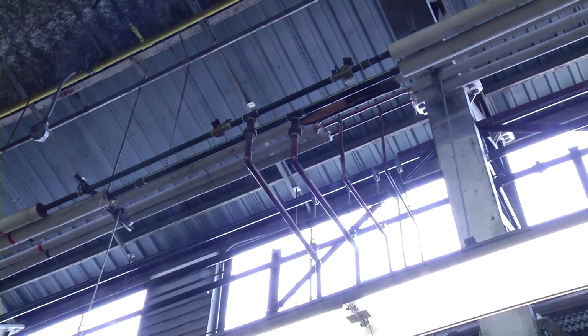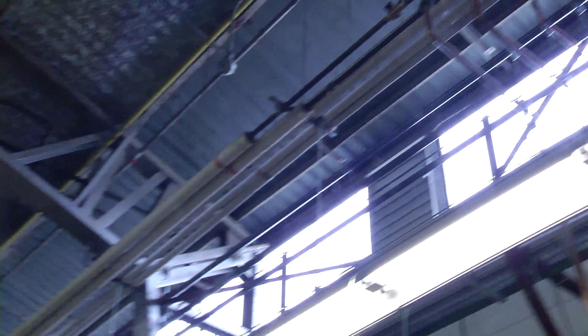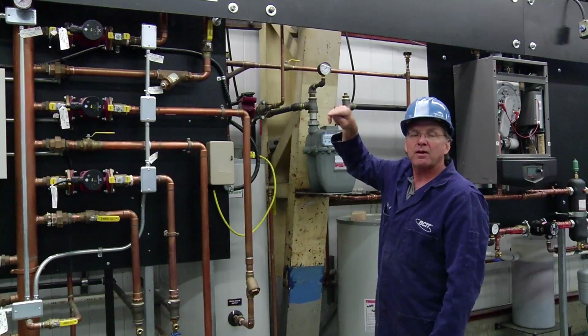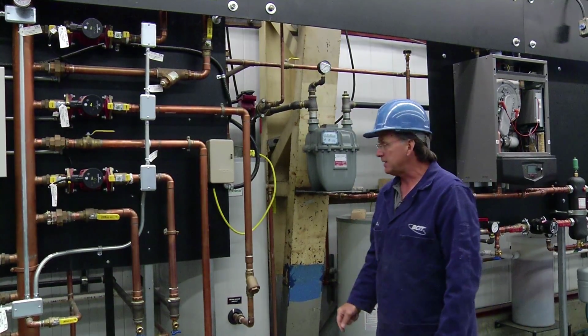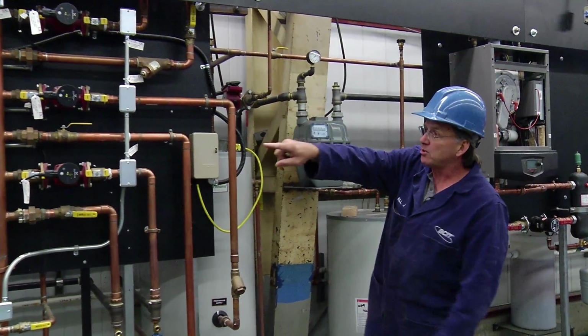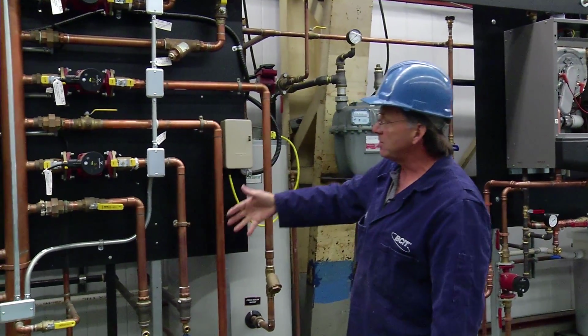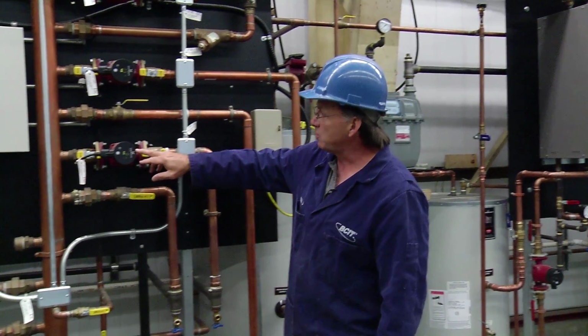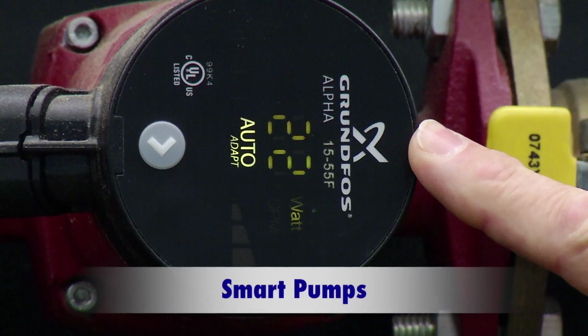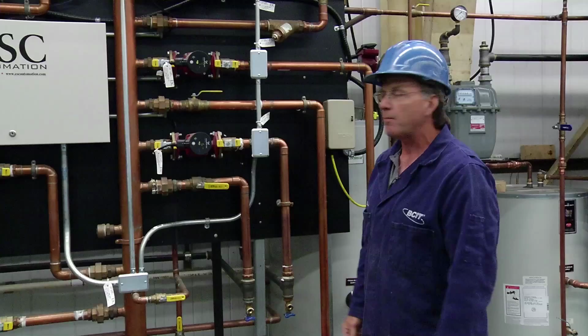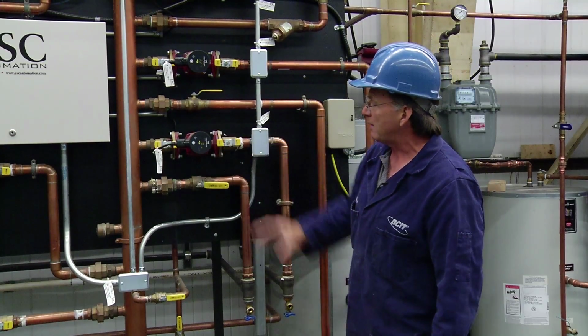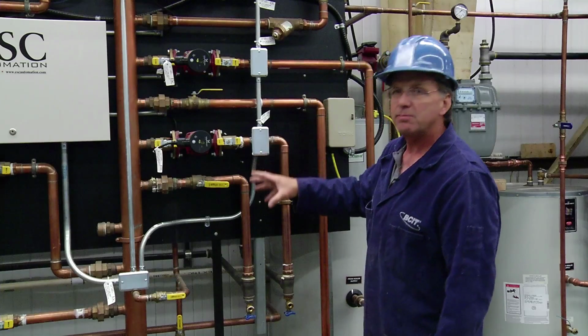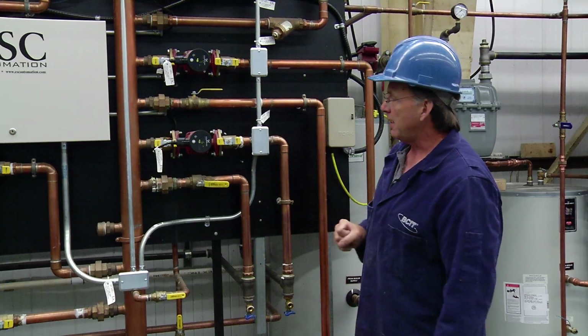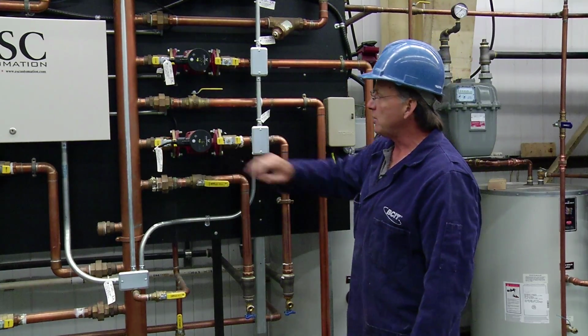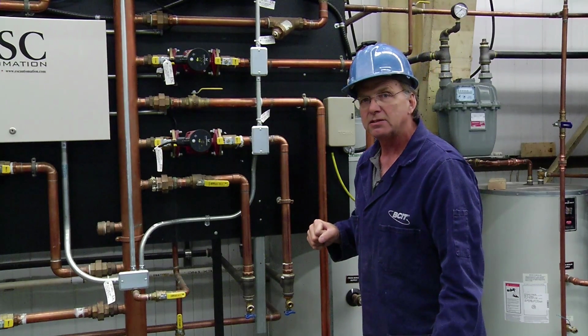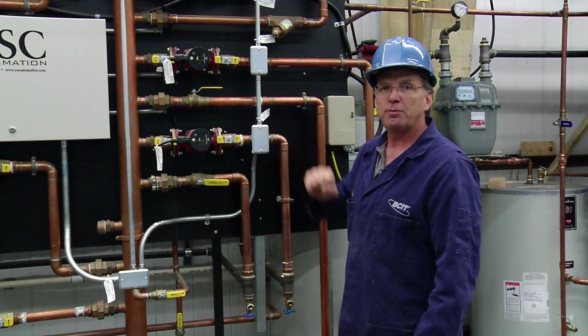We also have lines coming up and going overhead. Those are going to the air coils that heat the offices for all the different rooms in the building itself. All of that is fed from our two boilers through a mechanical system that actually features smart pumps. These smart pumps actually have an ability to change their RPM and their power consumption based on demand. So the computer control system could say that we only have to pump in so many gallons a minute, then they'll only pump so many gallons a minute.